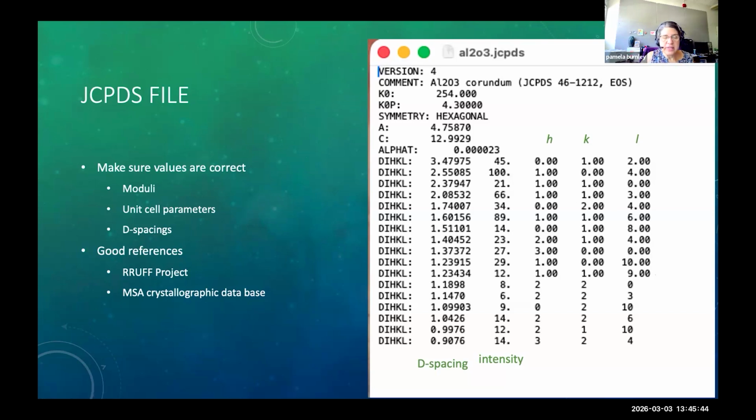And the reason you want to know that it's correct and nobody's gone in and edited stuff is that obviously if you pull up this data file in the MCA, and somebody has changed this number on you, the peak won't be in the right place. All right. Okay, so I'm going to figure out where I was. Go back here.